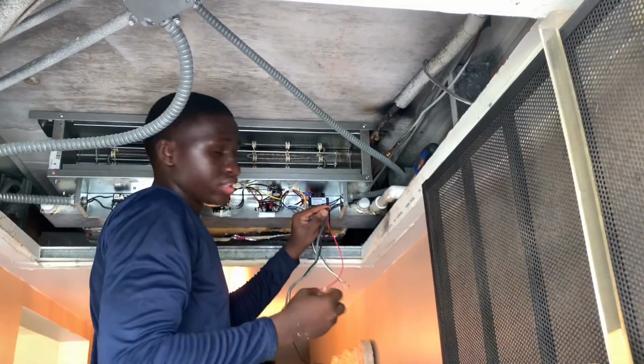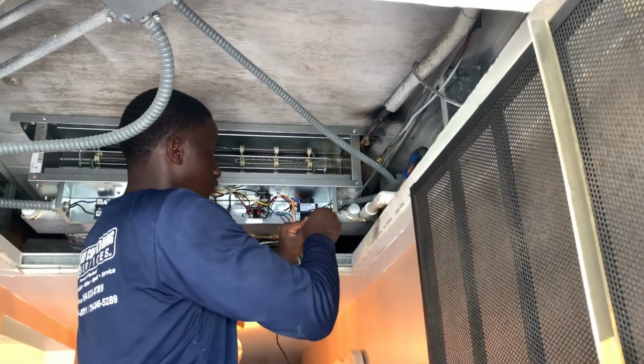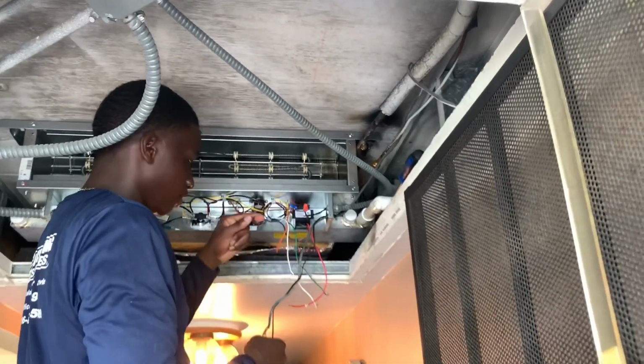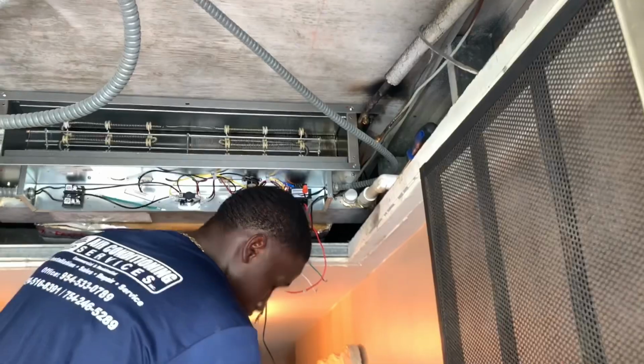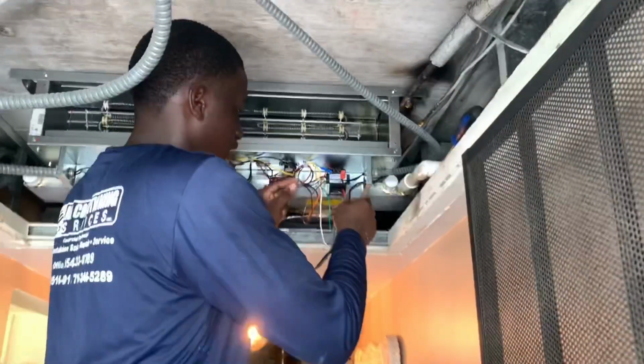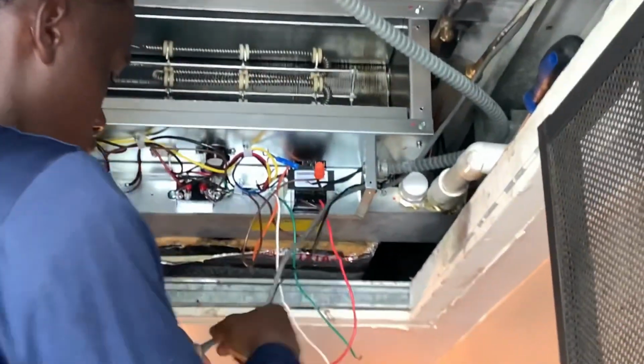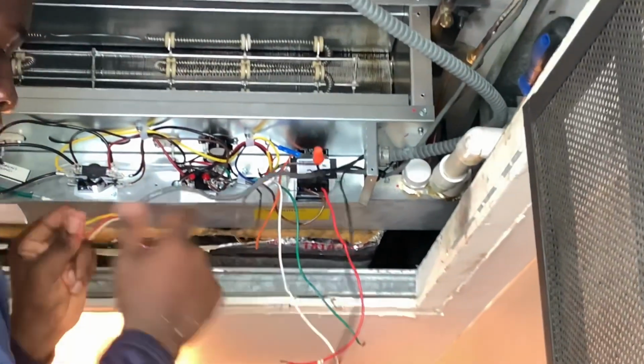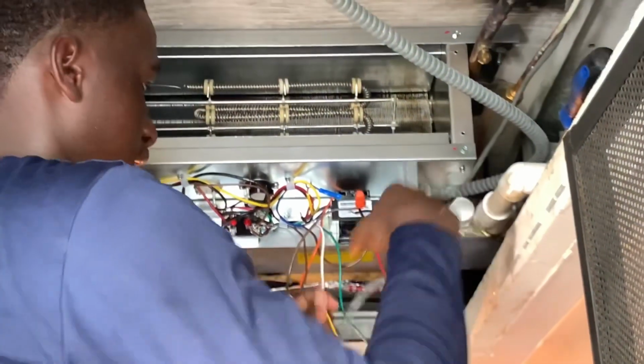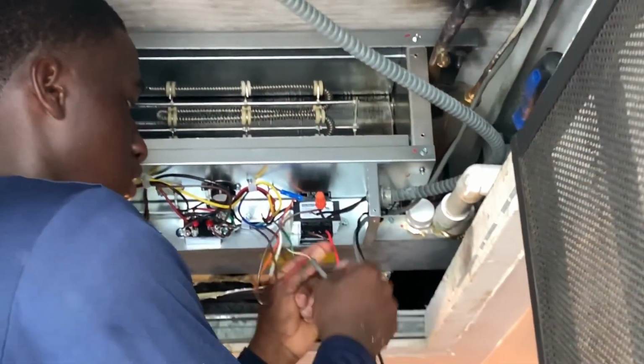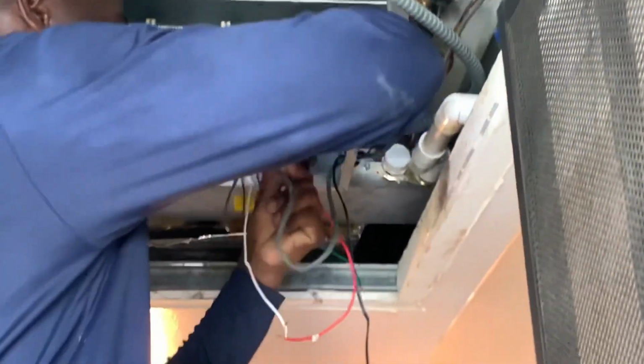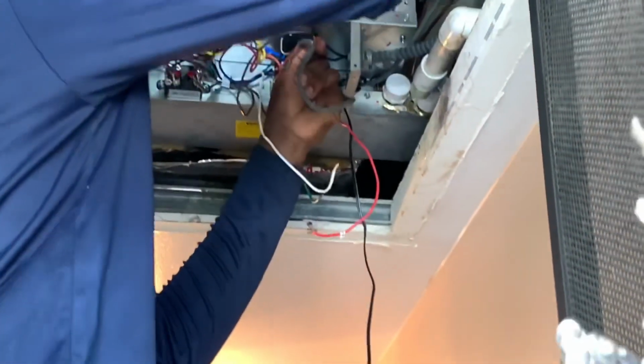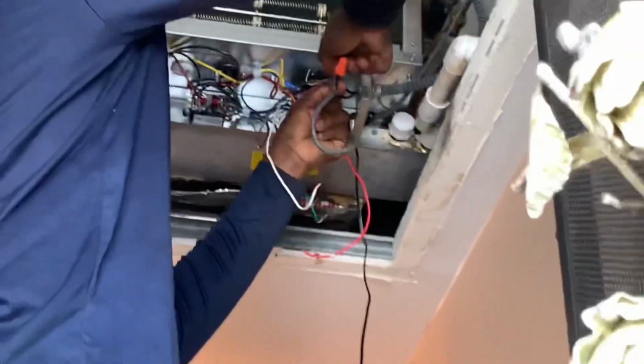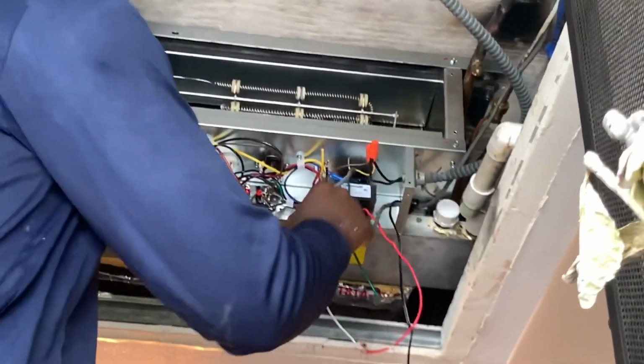Alright, right now we're gonna connect the contactor coil. This is the common from the unit, from the transformer, and then we're gonna connect the cool, which is the yellow, from the thermostat. We're gonna connect to the other side of the condenser coil, the contactor coil, and then that will energize the contactor coil to turn on.